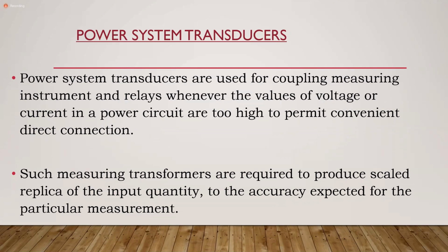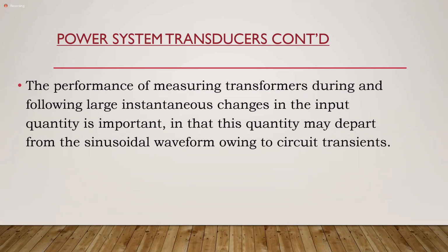And then we go further. The fact that you have harmonics means that it may impact how the protection system responds. As such, from a protection standpoint, we must be able to accurately represent what is on the system, whether it is sinusoidal, whether it is complex, whatever is there, it must be reflected at the output. So we speak about measurement from a revenue standpoint, but we also speak about faithful representation of the waveform, because that also has implications for how the relay, which receives this output, will respond. Okay? Any questions? Anything that I've said so far that is unclear?